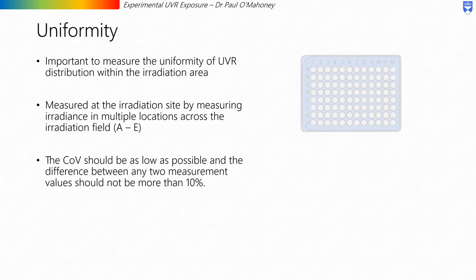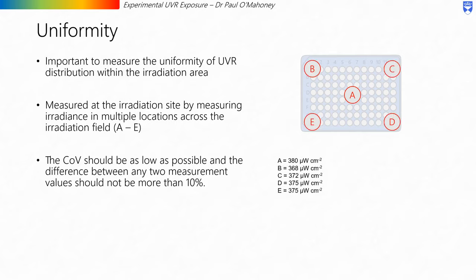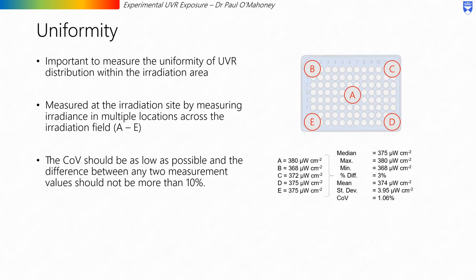Uniformity. It is important to measure the uniformity of UVR distribution within the irradiation area. For example, measuring the irradiance of a light source in the middle of a well plate at point A doesn't give any information about what the rest of the well plate is being exposed to. To measure uniformity, measurements can be taken at the four corners of the well plate. With these five measurements, we can get a variety of descriptive statistics about the UVR distribution. The coefficient of variation, or COV, should be as low as possible and the difference between any two measurement values should not be more than 10%. In this example, the maximum percentage difference is 3% and the coefficient of variation is 1.06%.